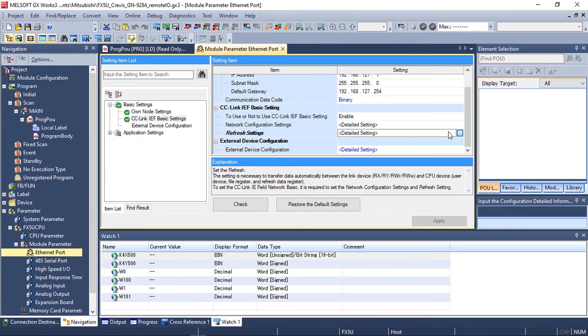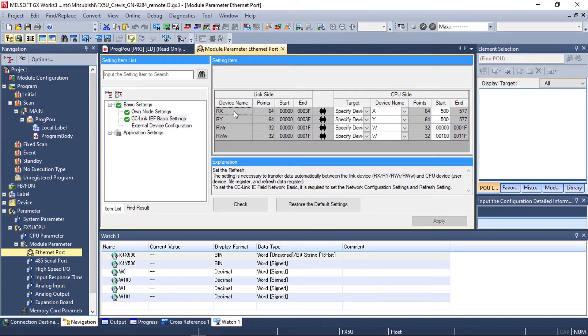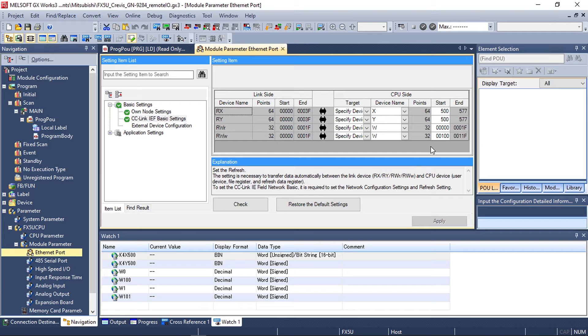Now we need to adjust the refresh settings to adjust the scan points that we want to read and the addresses they are read and written to. Our scan points for bits read and write start with 500 and our read and write scan points for words are 0 and 100 respectively.